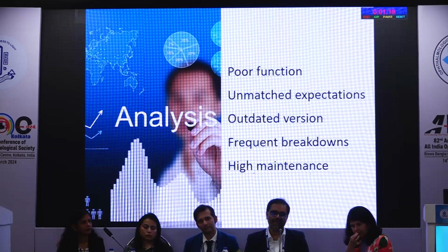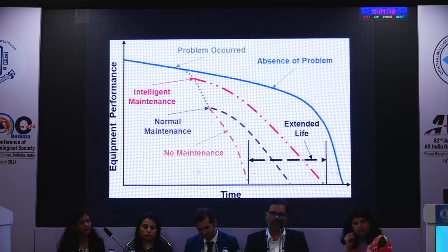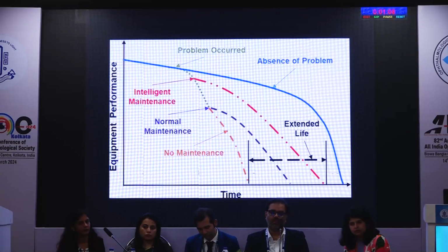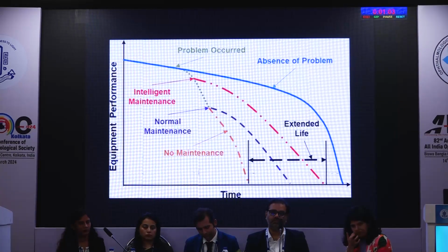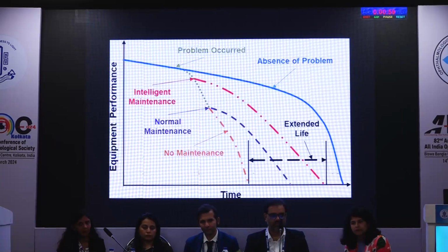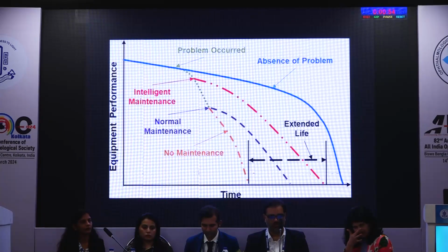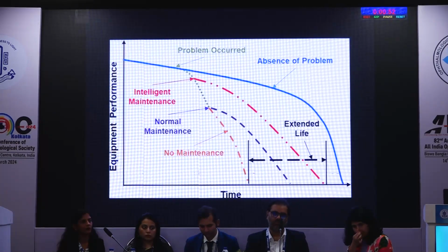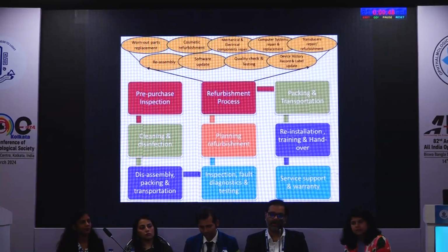The only one good reason probably a buyer could get a machine is that somebody's bought a new machine and he's winding up his practice for whatever reason. So how often is that going to happen? And then this is not often spoken about, end of life or longevity of machines. No matter how well a machine is maintained, there is only this much duration of time that it can work on. So when you are going for a second hand machine, you are going to get it somewhere in the middle. So in which part of this inevitable downward slope are you going to get your hands on the machine? You have no idea of actually knowing.